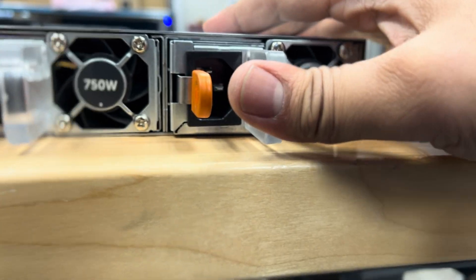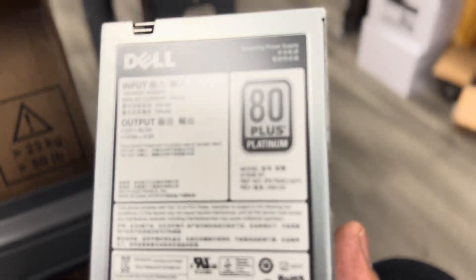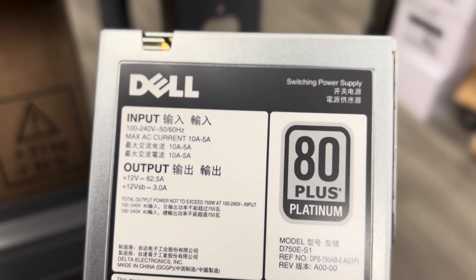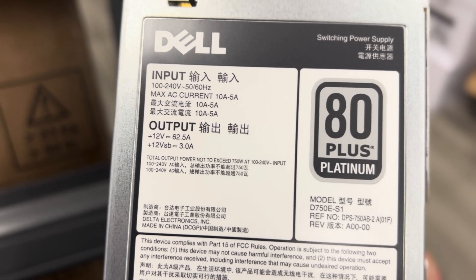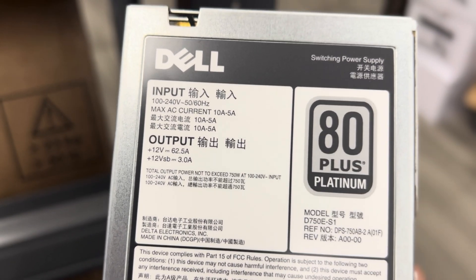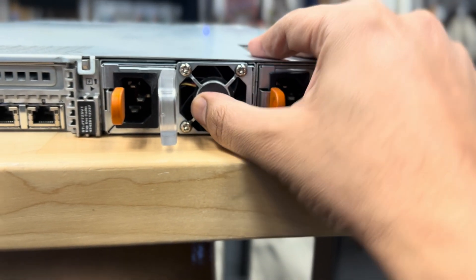If one of the PSUs goes bad, you can just press this with a little pressure and it comes out. I'm holding my phone with the other hand so it's a bit hard, but you can see I can pull it out. Looking at the label: it reads 100 to 240 volts, so it will work with both 120 and 220 power. In data centers it's usually 208 volts, and it will work fine with that.